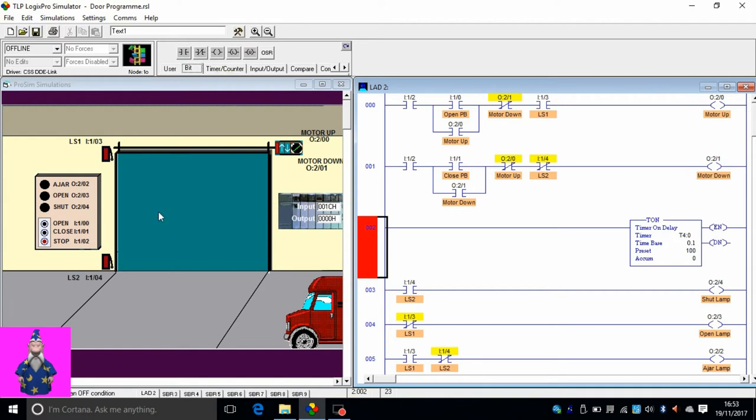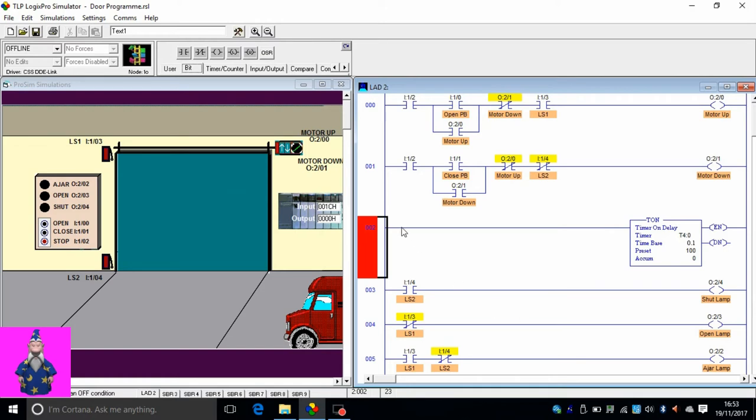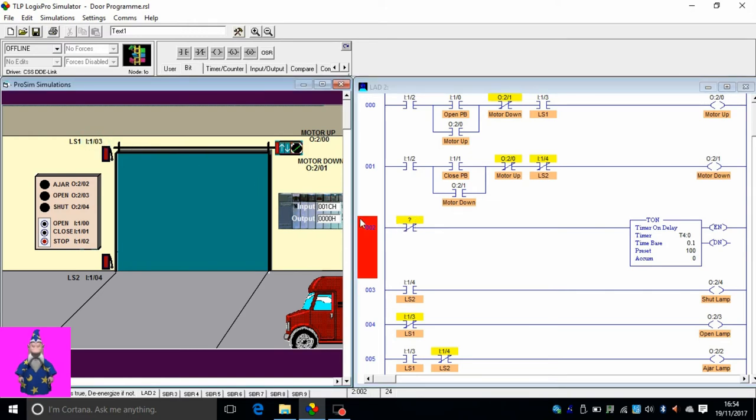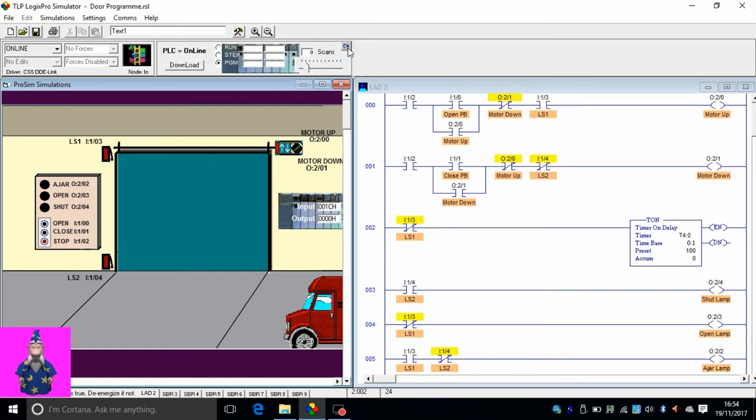Now we need a contact of this limit switch I1/3. What contact do we need? Do we need a normally open contact or a normally closed contact? When the shutter is completely opened, the limit switch is open, so we need a normally closed contact. When it's closed, the timer will count. This on its own won't do anything, and we can try this and see what happens.